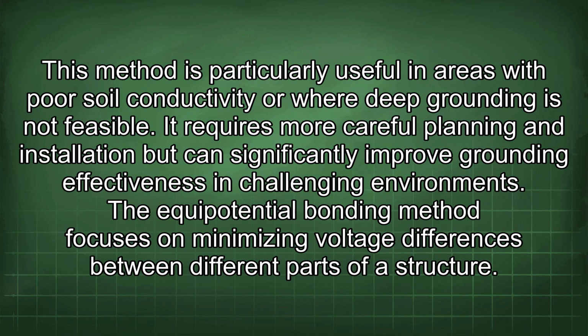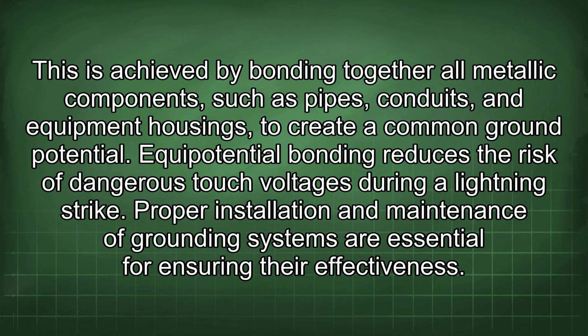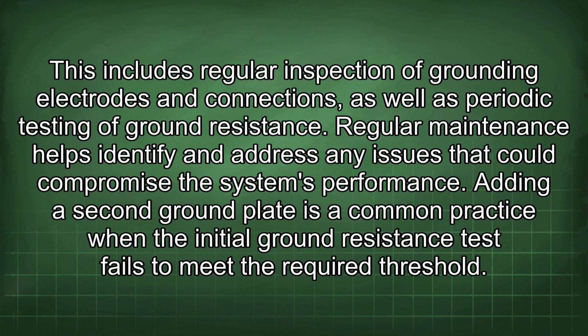The equipotential bonding method focuses on minimizing voltage differences between different parts of a structure. This is achieved by bonding together all metallic components such as pipes, conduits, and equipment housings to create a common ground potential. Equipotential bonding reduces the risk of dangerous touch voltages during a lightning strike. Proper installation and maintenance of grounding systems are essential for ensuring their effectiveness. This includes regular inspection of grounding electrodes and connections, as well as periodic testing of ground resistance. Regular maintenance helps identify and address any issues that could compromise the system's performance. Adding a second ground plate is a common practice when the initial ground resistance test fails to meet the required threshold.